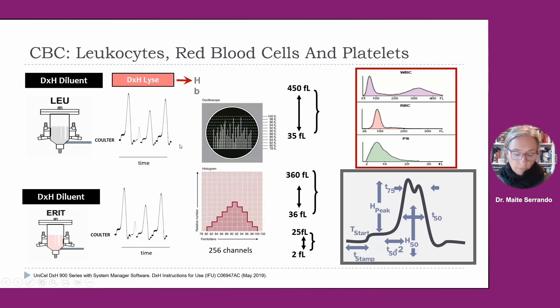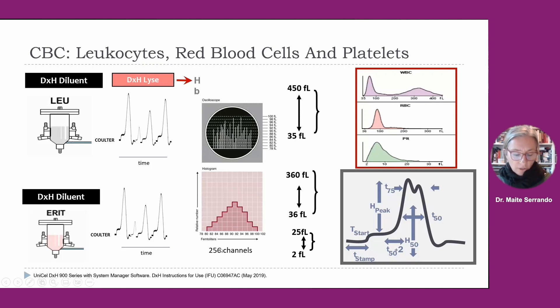The system manager processes all these measurements, which include coincidence correction, voting, generation of 256-channel histograms for white blood cells, red blood cells, and platelets. And always remember that we have interference correction for non-cells, fragments, and double cells.